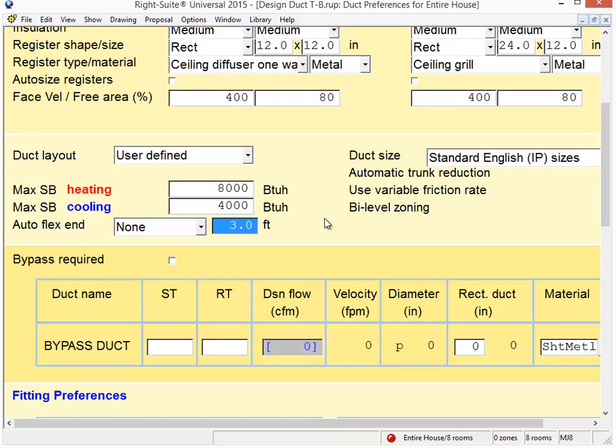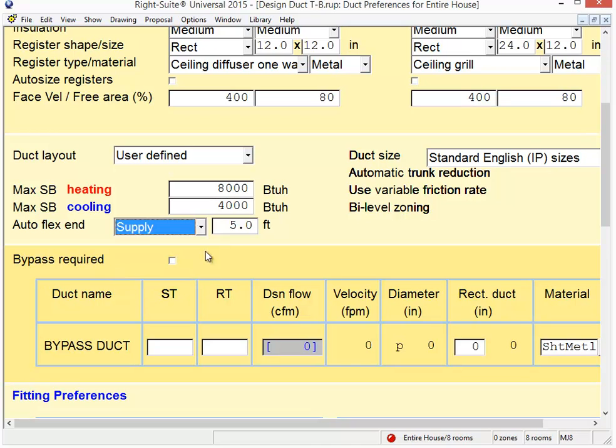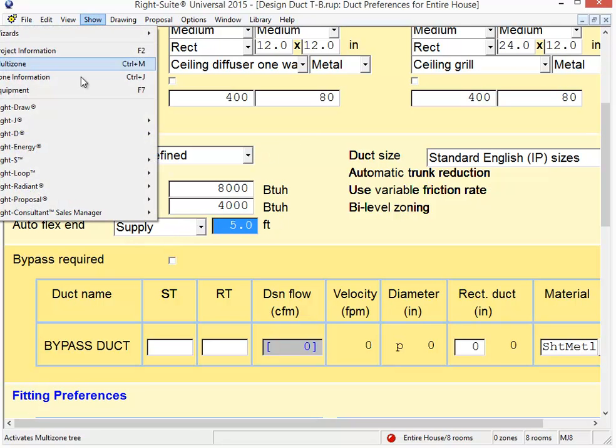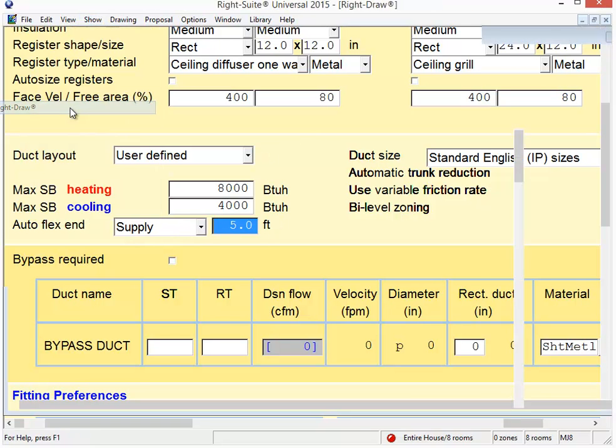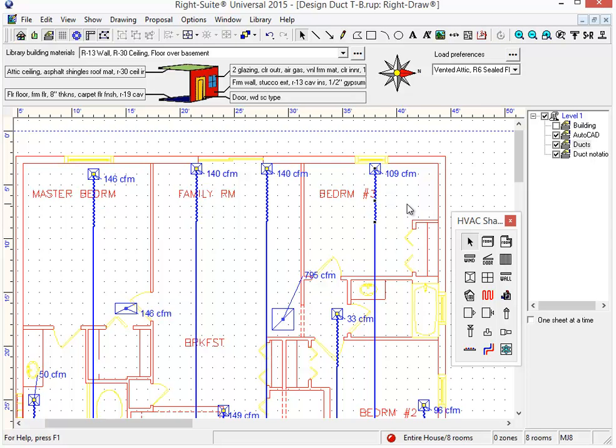And it gets trickier the more times you run this. So I'm going to say that I use five foot lengths of flex and I choose supply as my option. Remember, it's very helpful to set the length before you choose what will have the automatic ends. But now if I go back to my drawing screen, I'll see that each of these ducts ends in a piece of flex duct, which I could bend, although most of the time you find that these are going to be running straight. But it has all the properties of flex duct and will behave like flex duct, where the rest is traditional round sheet metal.